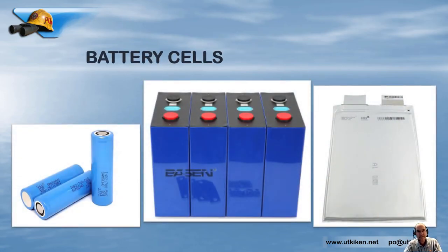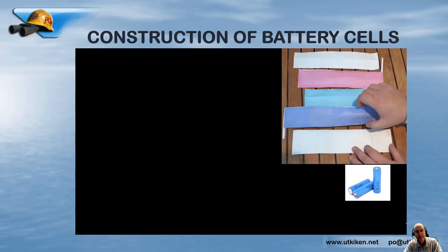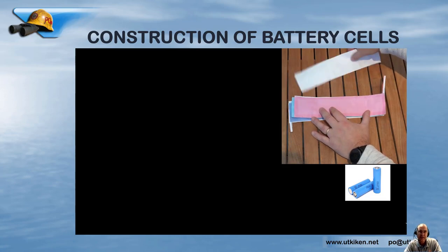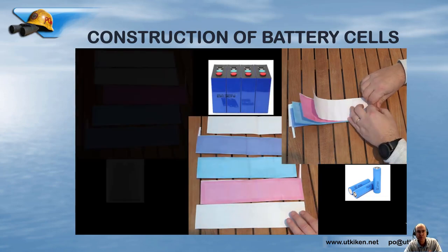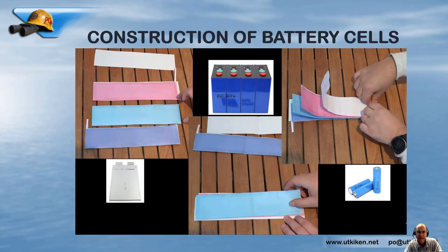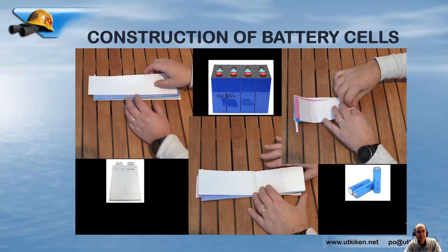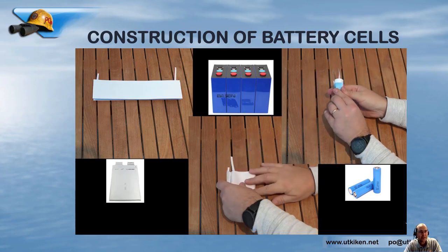There are a couple of different designs of battery cells. To the left we have a cylindrical cell, in the middle a prismatic cell, and on the right a pouch cell. That design matters in how they react to fire when within a battery module. They are all built basically the same way: sheets of cathode, electrolyte, anode, and an insulating layer — what you do with those layers after that determines the cell shape. For a cylindrical cell you roll them; for a pouch cell you stack them; for a prismatic cell you fold them in a slightly wider way.